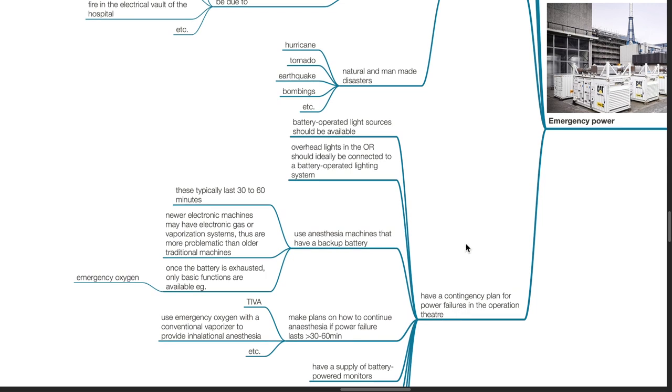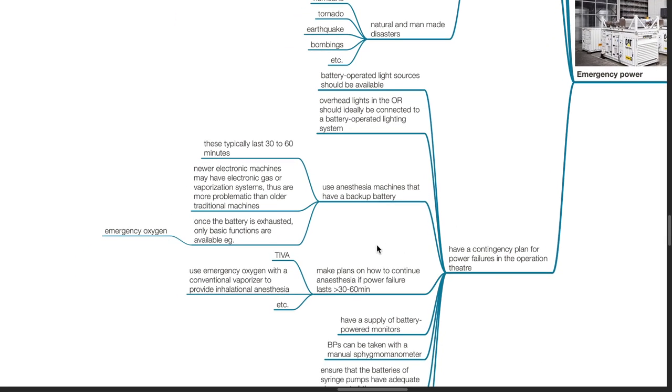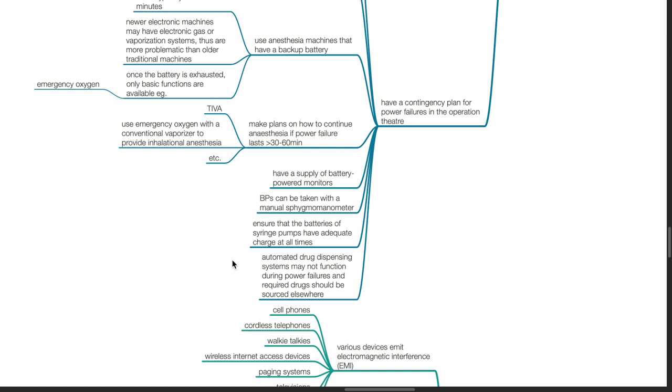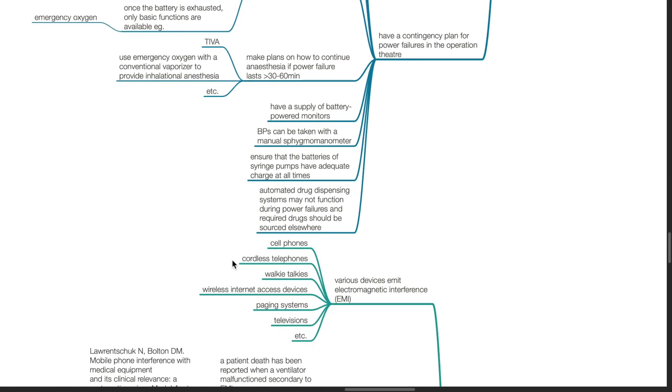Anesthetists should have a contingency plan for power failures in the operation theater. Battery-operated light sources should always be available. Overhead lights in the OR should ideally be connected to a battery-operated lighting system. Use anesthesia machines that have a backup battery; these typically last 30 to 60 minutes. Newer electronic machines may have electronic gas or vaporization systems, thus are more problematic than older traditional machines. Once the battery is exhausted, only basic functions are available such as emergency oxygen. Make plans on how to continue anesthesia if power failure lasts more than 30 to 60 minutes, such as by use of TIVA or use of emergency oxygen with a conventional vaporizer to provide inhalational anesthesia. Have a supply of battery-operated monitors. Blood pressures can be taken with a manual sphygmomanometer. Ensure that batteries of syringe pumps have adequate charge at all times. Automated drug dispensing systems may not function during power failures, and required drugs should be sourced elsewhere.